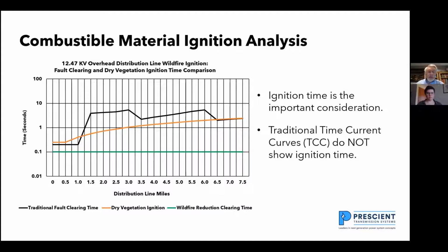So if I disable reclosing, I'm only going to get one trip. In addition to disabling reclosing, I'm going to use more sensitive settings. The more sensitive settings I use should be a function of the ambient conditions where I am. In the rainy season, it's okay to use the black clearing line because the vegetation ignition line during the rainy season wouldn't be this red line here, but it will be moved up because there's a lot of moisture. You have to get the moisture out of the combustible material before it catches on fire. So what we're looking at is dynamic settings, and the dynamic settings will be a function of the ambient conditions where we are.